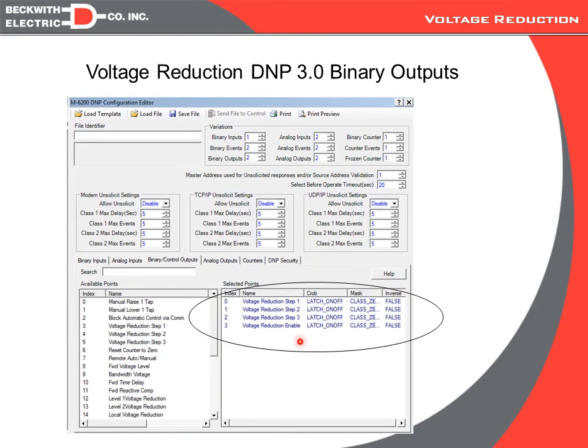Next will be the binary outputs. So first of all, we can have a command down at the bottom, a latch on, latch off, to enable voltage reduction. So if we send a latch on, it enables it, a latch off disables it. Then we have latch on, latch offs for each of the three individual stages. And a latch on places that in voltage reduction, and a latch off takes it out of voltage reduction. Now, as an aside, if we were in level 1 reduction and we sent a latch on command for level 2, that would take it out of level 1 and place it in level 2. So when you're going from one level to another, you don't have to come out of the first level to enter the second. But if you just want to come out, then you would have to send a latch off.